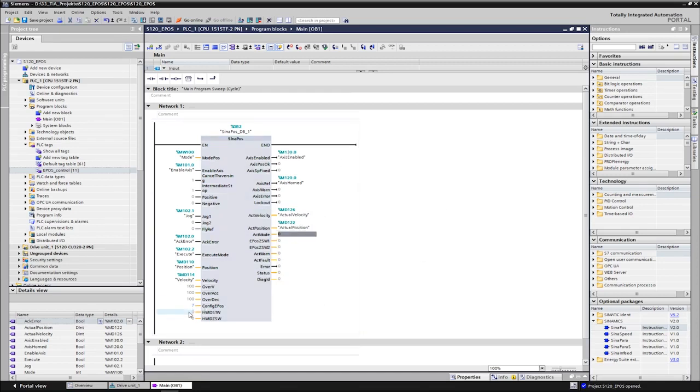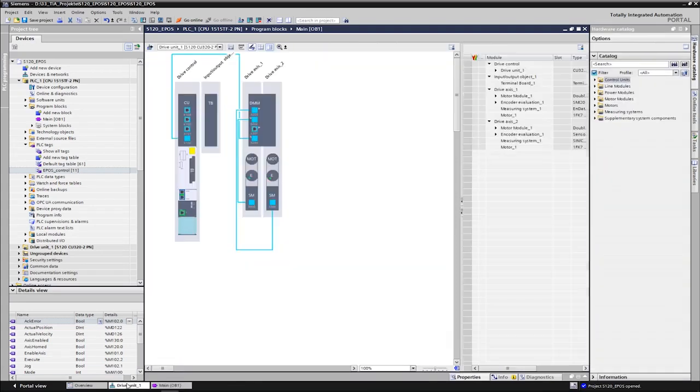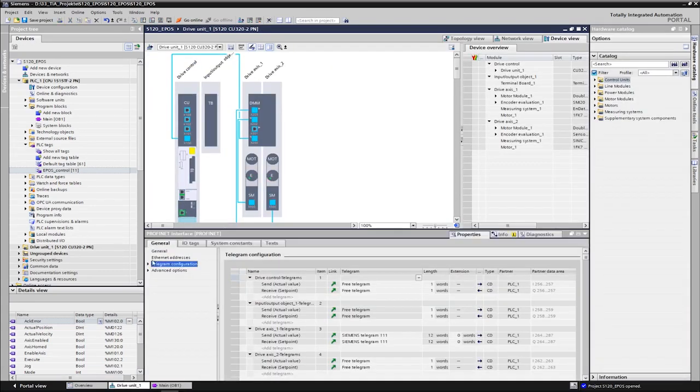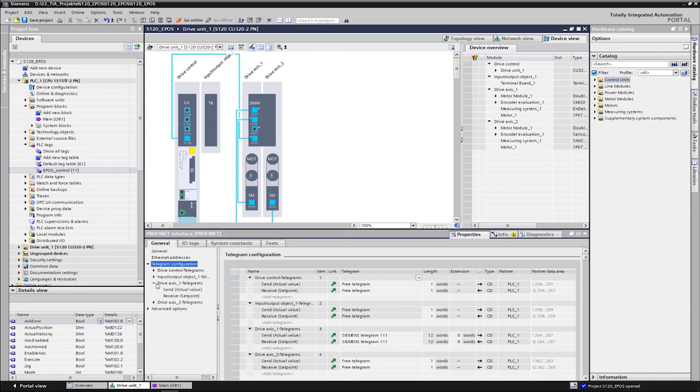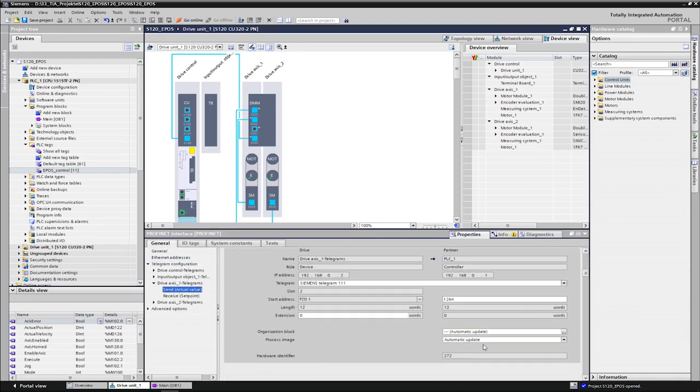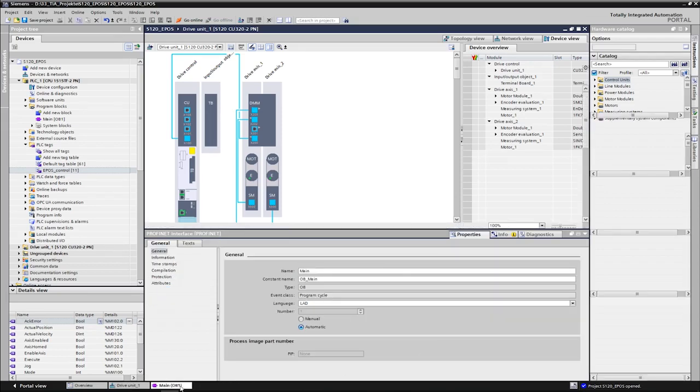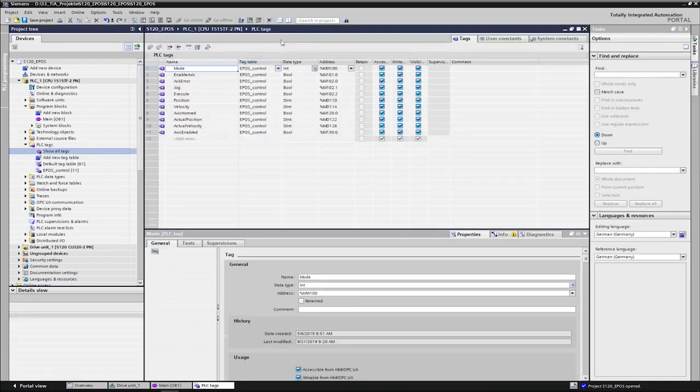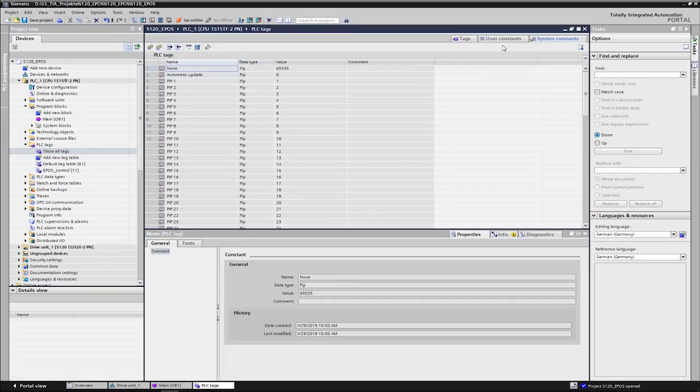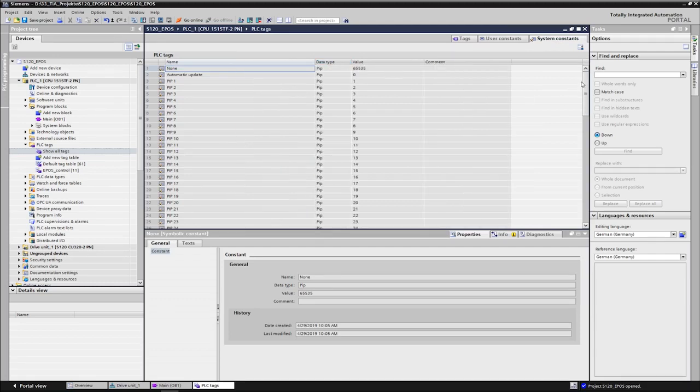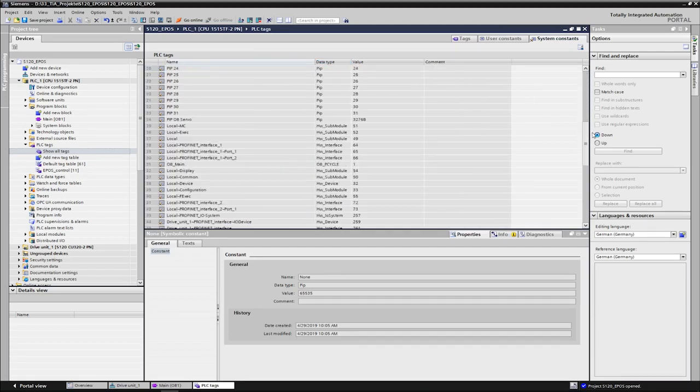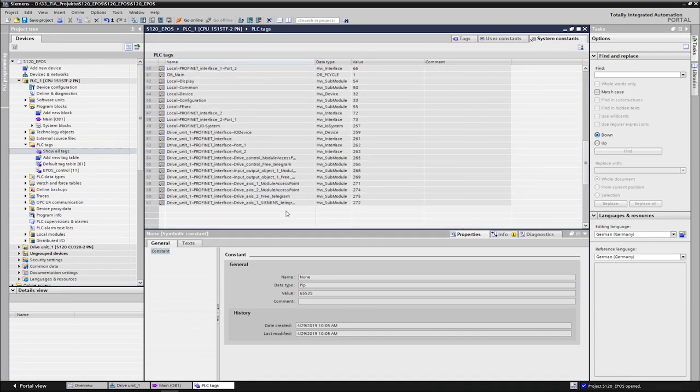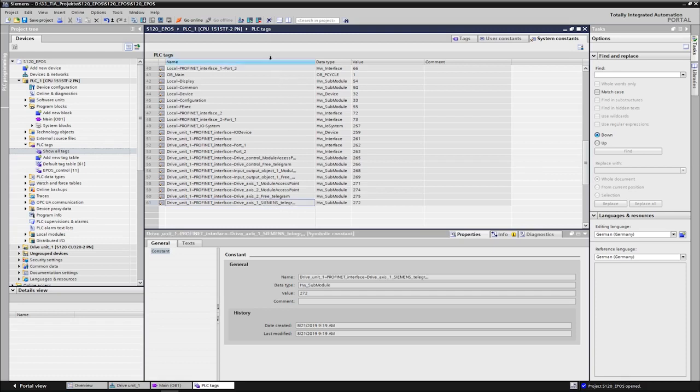Then we come to the inputs that are important for the correct operation of the communication. We have to inform the block about the hardware ID of telegram 111 with which the drive block should communicate. The hardware IDs are automatically assigned by the PLC when the peripherals are networked. We find the hardware ID of the telegram, for example, in the telegram configuration of the drive or in the system constants of the PLC.